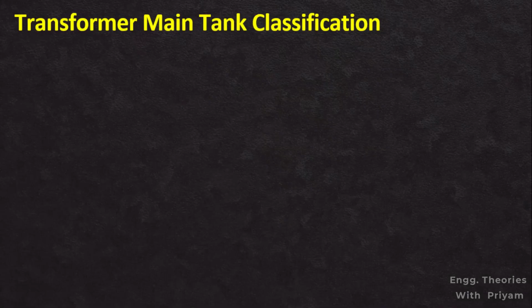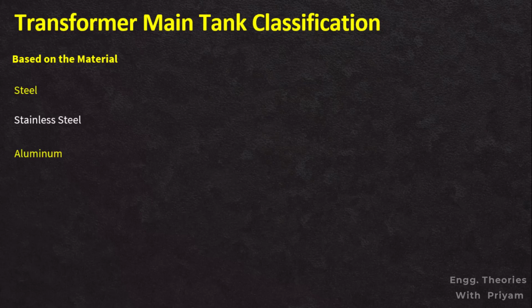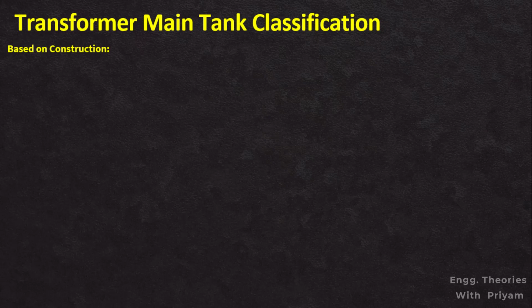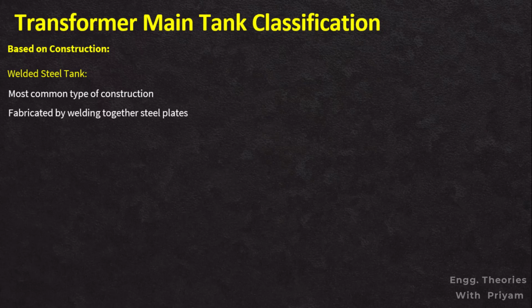The classification can focus on different factors like material. In terms of material, the transformer main tank can be constructed with steel, stainless steel, aluminum, and sometimes composite materials, which aim for lighter weight and improved insulation properties. Based on the construction, there are several types of transformer main tank, like the welded steel tank. Welded steel tanks are the most common type of construction for the transformer's main tank. They are fabricated by welding together steel plates to form a sturdy enclosure. Welded steel tanks offer durability, strength, and ease of manufacturing.